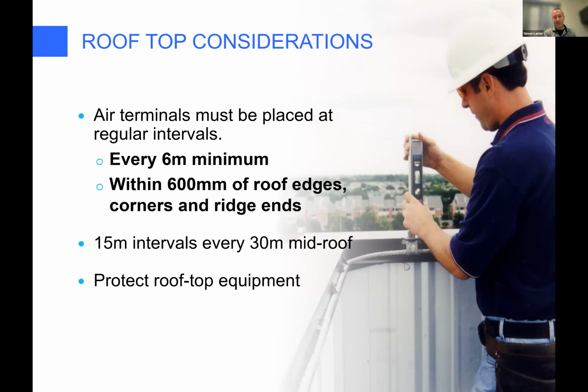So all of this information I'm going to give you now as to where the lightning rods are supposed to go—it's a relatively new thing in Canada, but only because we finally harmonized the codes cross-border in this B72 2020 edition with NFPA 780. Before 2020, I would give presentations like this and tell people not to pay attention to the CSA code. But now I can tell you to pay attention to it, because it's actually a decent one now.